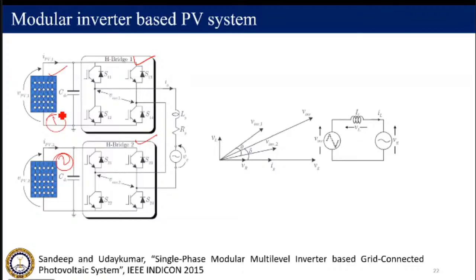So this is the phasor diagram and this is the equivalent circuit. The inverter is basically generating a switched waveform that you can see here, and the grid has a fundamental voltage, with a filter L. This is the voltage VL, and this is the voltage VG. We are going to inject a current IG which is in phase with VG, meaning we operate at unity power factor.